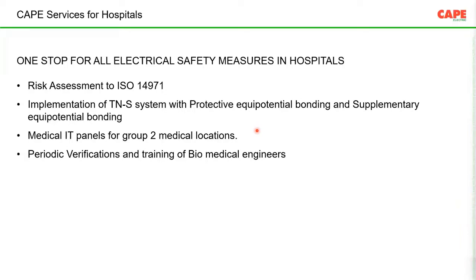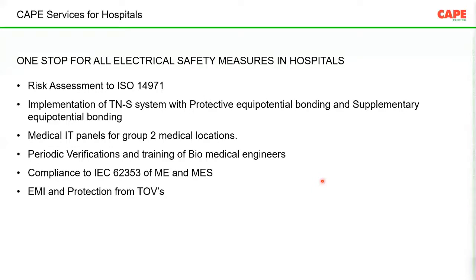Sometimes you may have to check your UPS and your generator once in 3 months or once in 6 months. So calling a third party and doing this test will be quite difficult. Also, imagine you are getting new equipment every time. Depending on a third party will be very difficult. So we train your biomedical engineers to handle the day-to-day needs of the technical requirements. Compliance to IEC 62353 for medical equipment and medical equipment systems.